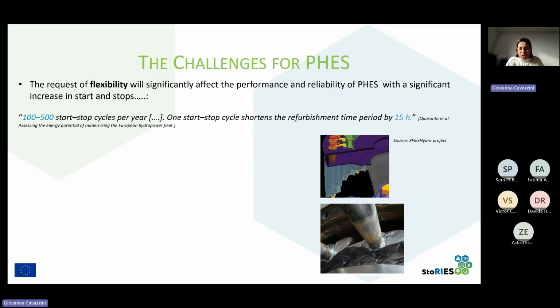But this comes at a certain price. It has been estimated in this study that one start-stop cycle shortens the refurbishment time period by 15 hours. In the best scenario, the plant will be required to have 100 to 500 start-stop cycles per year, but in the worst scenario, this technology can be required to have 30 start-stop cycles per day. You can imagine the impact this has on the reliability and life of the equipment.